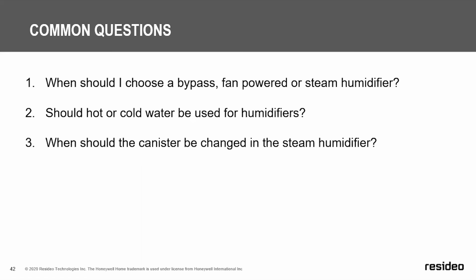And then finally, when should that canister be changed in the steam humidifier? Well, over the years, I've seen a couple of rules of thumb. I've seen folks who replace them at the end of every season, so they're ready to go at the beginning of the next year, so during spring tune-ups is a good time to change the canister. I've seen contractors educate the homeowner on how they can change the canister very easily themselves, and then leave the canister there for them to change when the LED indicator says it's time. And I've seen people who change them at the beginning of every season. So really all three are correct. It's really a personal preference for your business. If it's installed at a home where you have a standard service contract and you're going to be there annually anyway, you could just pick a time and put it in every year, so long as you're changing it. Exactly.